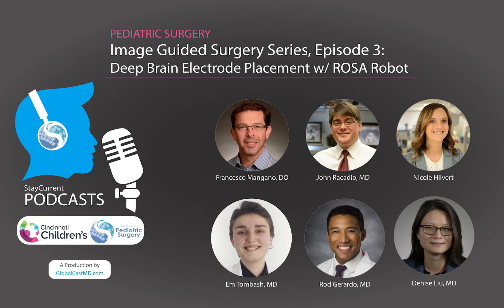Can you tell us a little about what facial registration takes? Nicole Hilvert, program manager for the Image Guided Surgery program, explains: facial registration is completed preoperatively through the patient's CT scan. We take a significant number of points on the face — including the forehead, eyes, nose, and temples — which allow us to get within two millimeters of accuracy for registration of the brain. That whole process takes about 15 to 20 minutes, including getting the patient in pins, locking the robot to the table, and going through the registration process.